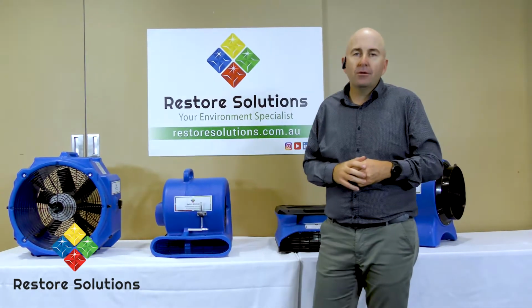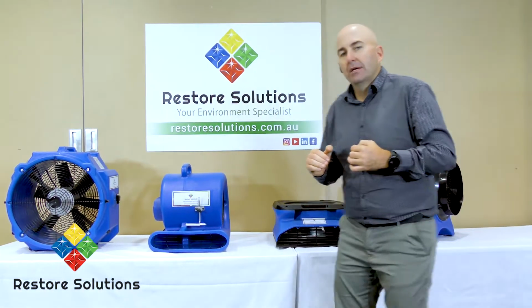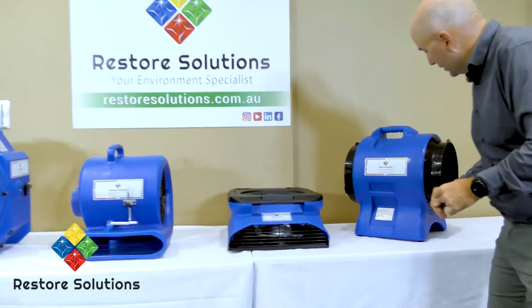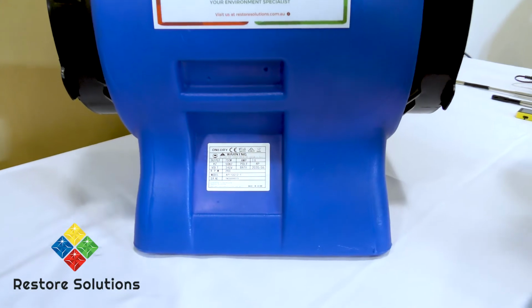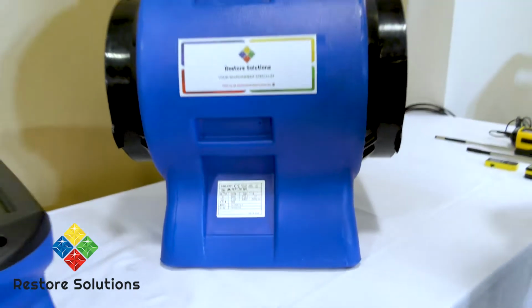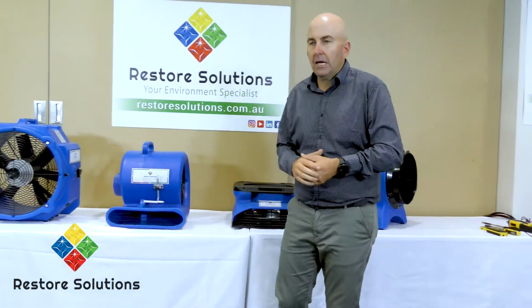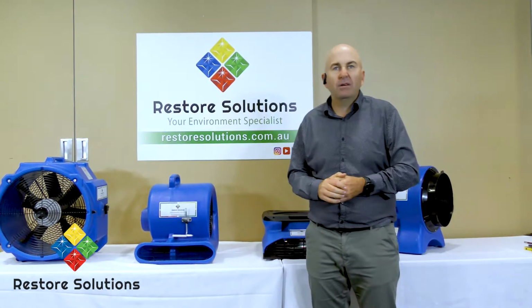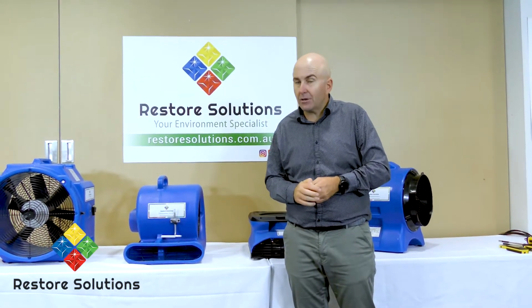Now, equipment really needs to be RCM compliant. Now, I don't know if we can get a little bit of a close-up here, but if we get a little bit of a close-up, we're looking for this little triangle with a tick in it. Okay? That's our RCM compliancy. So people will always say, well, they're CE approved. Okay? That doesn't mean much over here. In Australia, might mean something in Europe, doesn't mean in Australia.